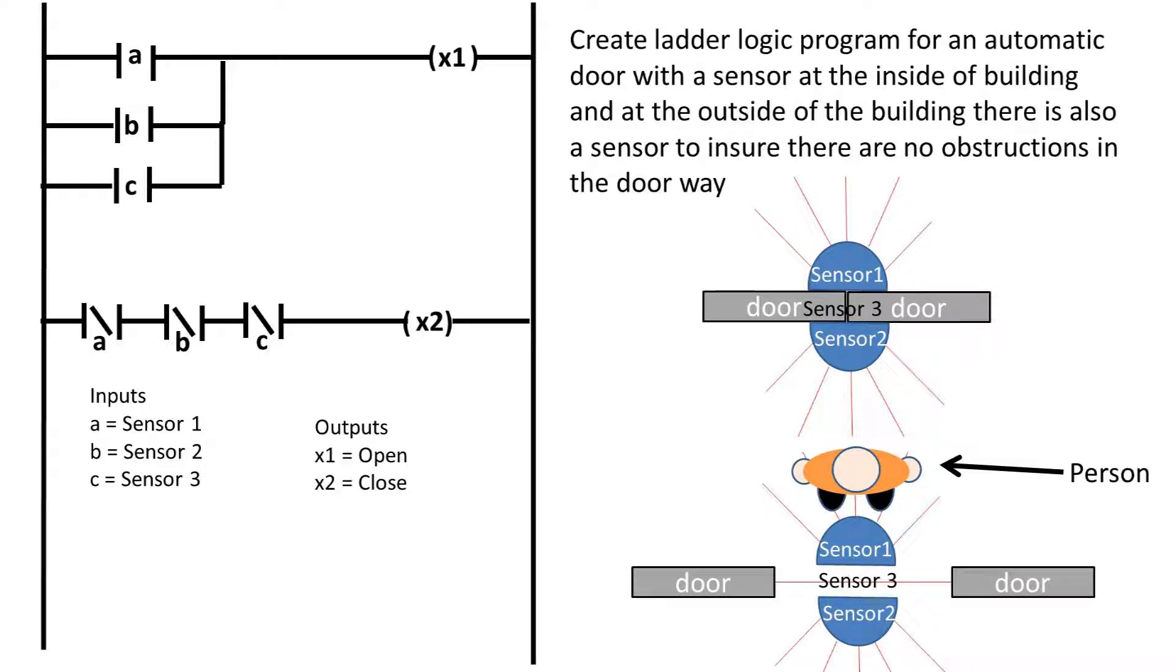Next, we have to make sure that the door only closes when all of the inputs register a false or off input. This sounds like an AND function to me. We can use normally closed contacts in series connected to a coil that closes the door.